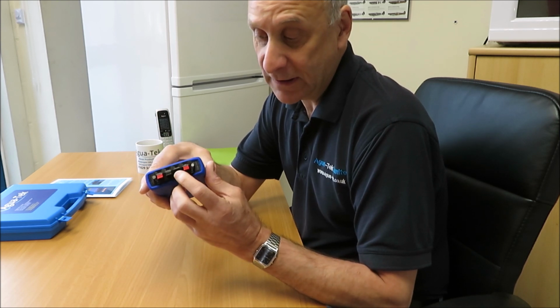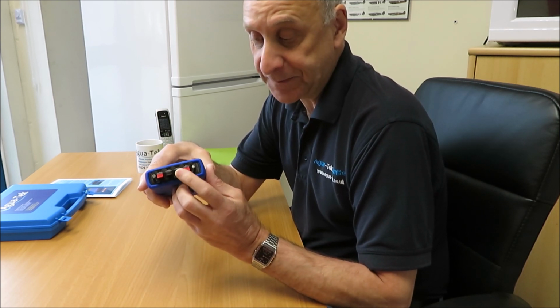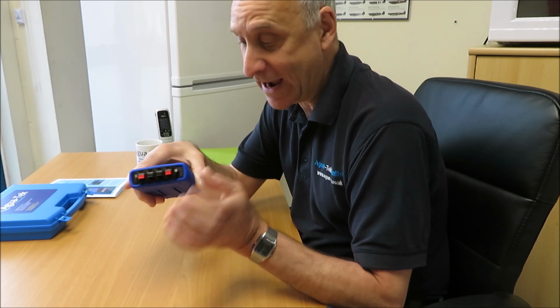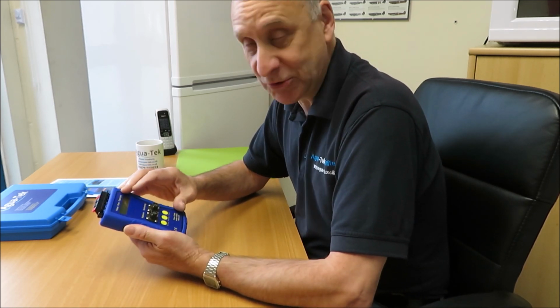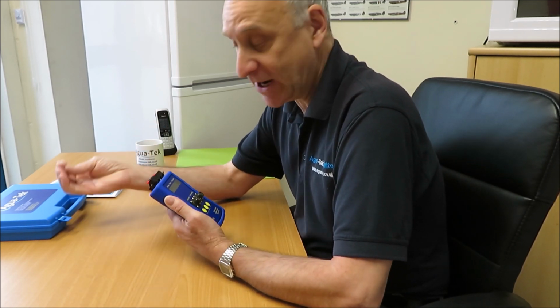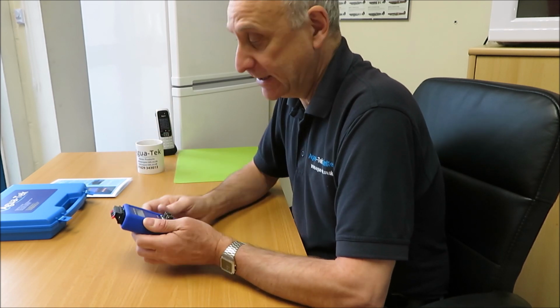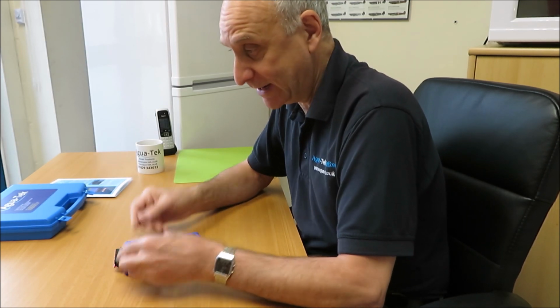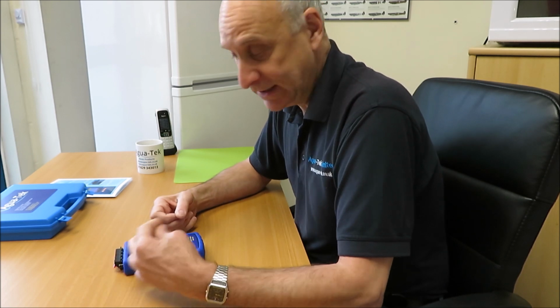The other two connections there are capable of putting a pulse out. So this pretends it's a water meter and actually puts a pulse out so that you can test a data logger to see if the flow cable that you've got connected to the data logger is actually working.